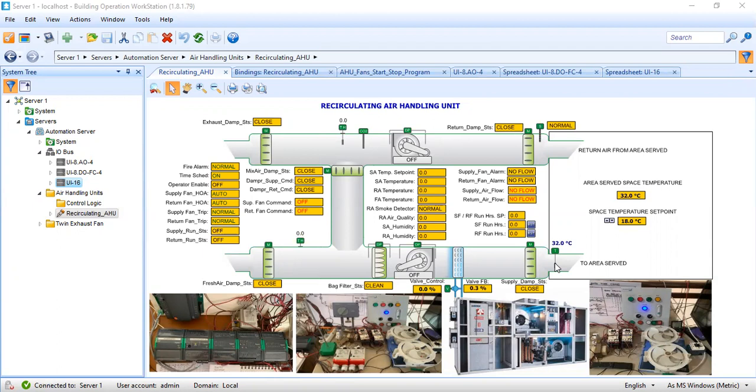Okay, now let me explain again. Now I have here, I have put a temperature set point. Okay, let's say this air handling unit will try to maintain this temperature here, 18 degrees centigrade. So our cooling valve, by the way, this is our cooling coil. Okay, this is the cooling coil. Now, the cooling coil has a supply and return, or supply here and return.